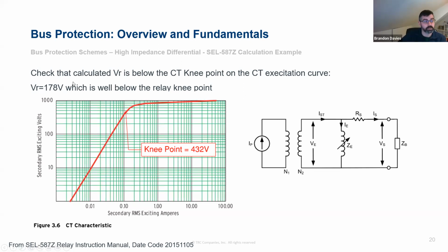So you want to check that to make sure you've got that amount of margin between your set point and your calculated VR and the performance of the CTs.